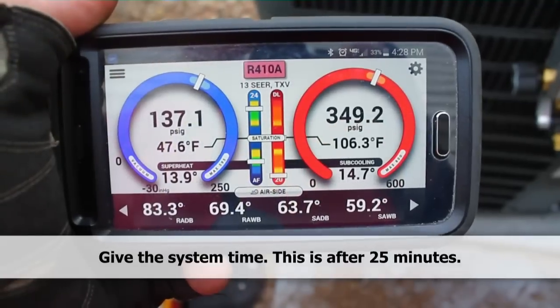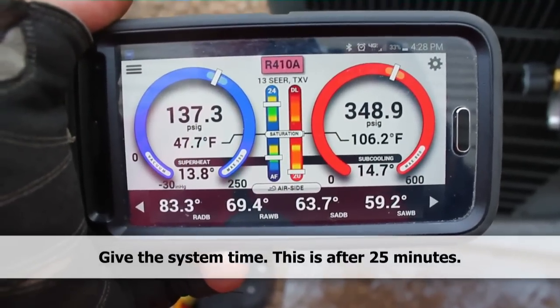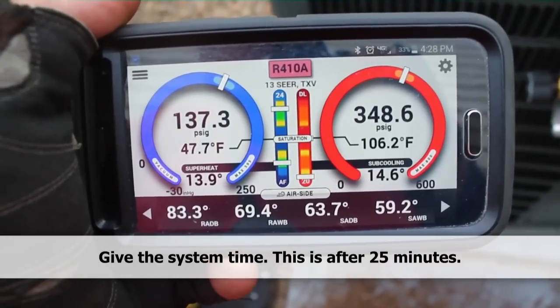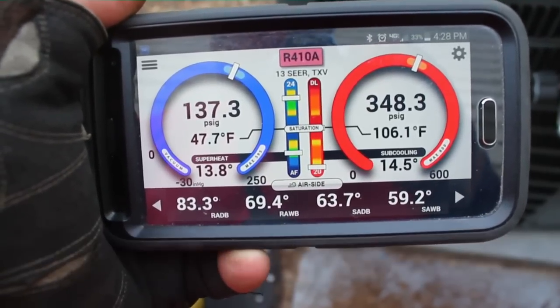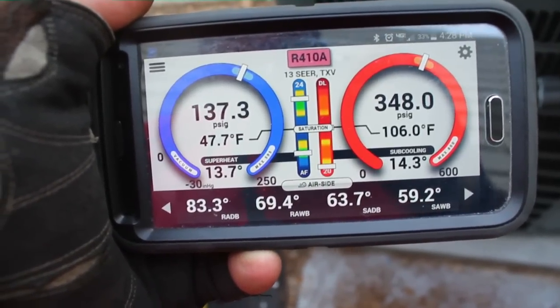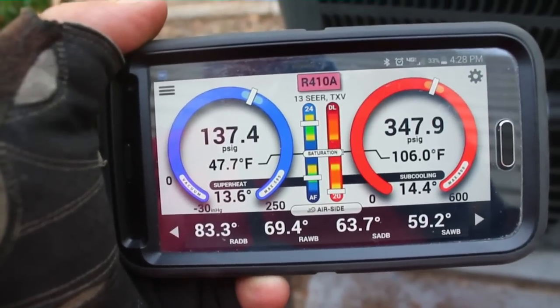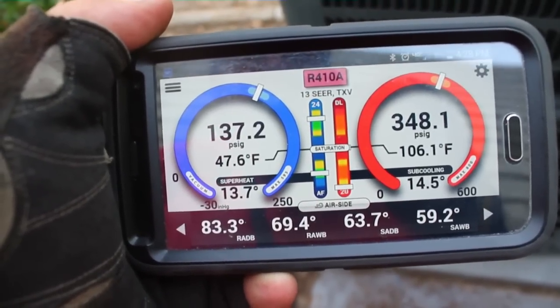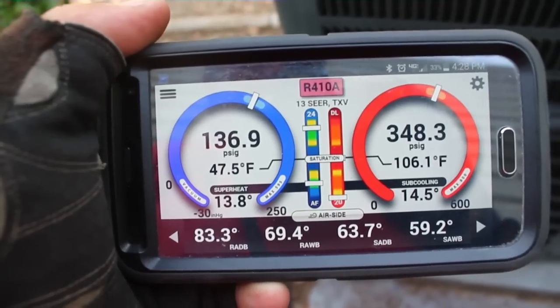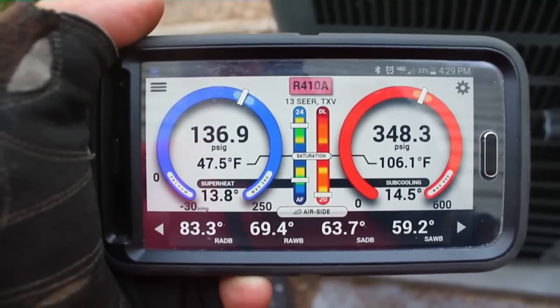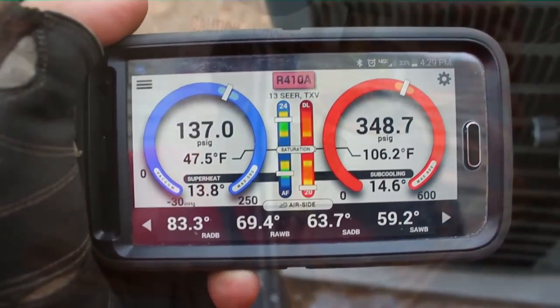As you can see guys, the subcooling is a little high. We didn't actually adjust anything yet. We've run it for about 25 minutes. Our subcooling is 14.5. I'd like to see it a little bit lower than that. We can adjust our TXV, bring the subcooling down and the superheat down, which is where it needs to be. So we'll go ahead and make that adjustment inside and see how it works out here.